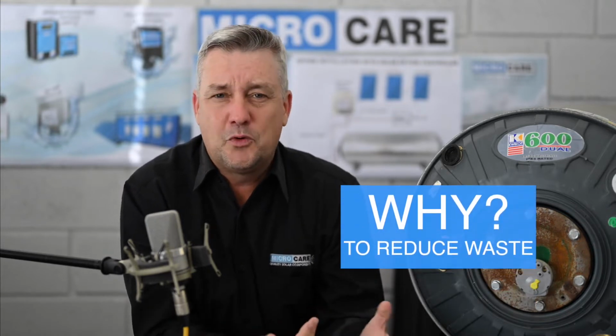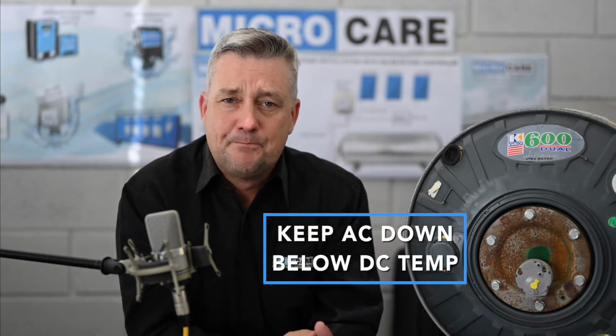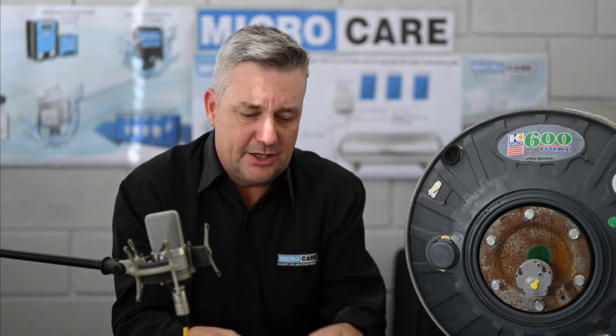And the reason for that is because we don't really want AC to have to warm up 55 to 60 degrees when you are setting the timer. That's a bit of a waste of energy. 55 is more than sufficient. So if it's looking with the timer or the Wi-Fi module, it checks temperature and it sees that it's 56 degrees, there's no need to switch Eskom on for 4 degrees. So keep the AC down below the DC, something like 55 on the AC side and 60 degrees on the DC side.